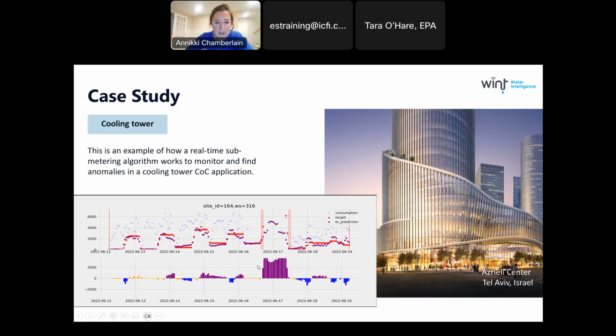So these guys are on this tower. You can see on the 17th, they have this predicted flow, and then they get this much higher use, which is inconsistent with what the learned pattern of the tower is. So that would send an alarm also. So they were able to resolve that. So I thought that was pretty cool. That's well beyond my level of expertise.